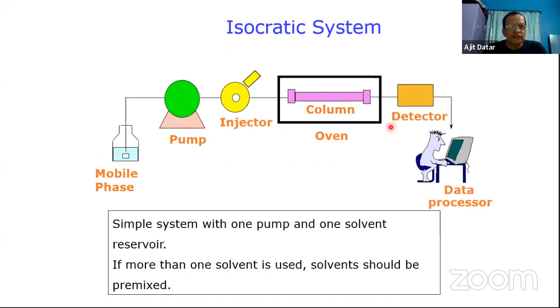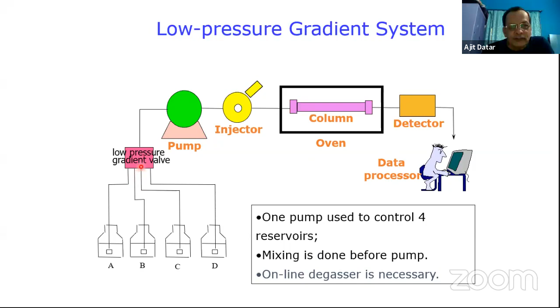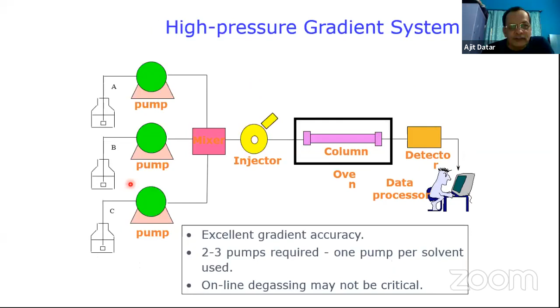And there are 2 methods of gradient system. One is with 3 pumps and 3 mobile phases separately. Here only 1 pump, but 4 mobile phases are mixed, and there's a slight difference between the way they are getting into the system, but the rest of the things are constant. So this is the difference between isocratic and gradient. In isocratic, even if you have 2 different solvents mixed together, the composition of mobile phase remains constant throughout the analysis time. So all the components are separated with the same composition of mobile phase.